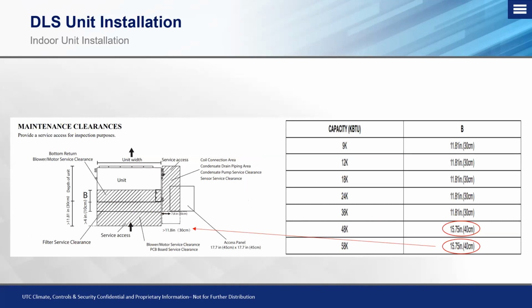Now, if we're dealing with a ducted unit that is installed vertically versus the traditional horizontal path, those same rules apply. So on the side with your refrigeration access fittings, we need at least 12 inches of clearance. Now that only changes when we step up to a larger ducted unit, such as the 4-ton and also the 58,000 BTU. And you can see in here I have circled in red. This requires just about 16 inches of clearance just because of how this access panel is on these larger style units. Now on the right-hand side, we still maintain that minimum of 4 inches. Okay, and again, this is a vertical style installation, not horizontal.